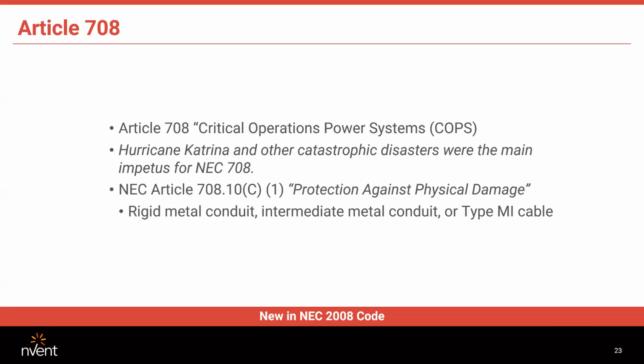So say you've got a police station or a fire station, and there's a local or national emergency where it's going to be used as a command center. Every feeder in that building must not only be 2-hour fire rated, but also must be protected against physical damage, and has to be either RMC, IMC, or type MI cable. You cannot use EMT.